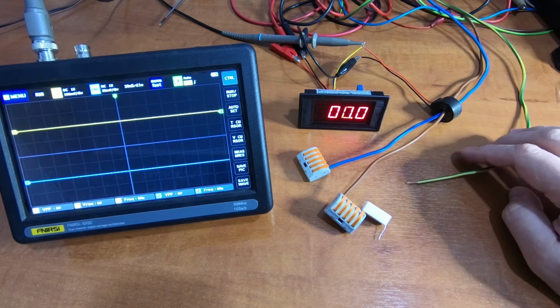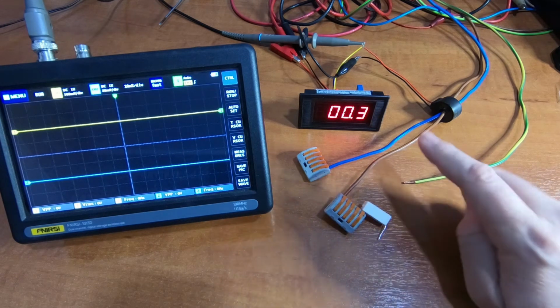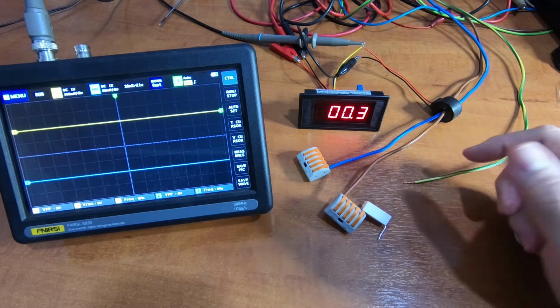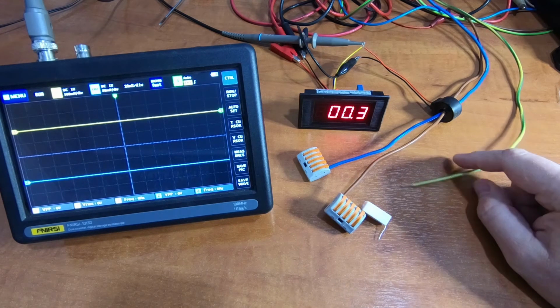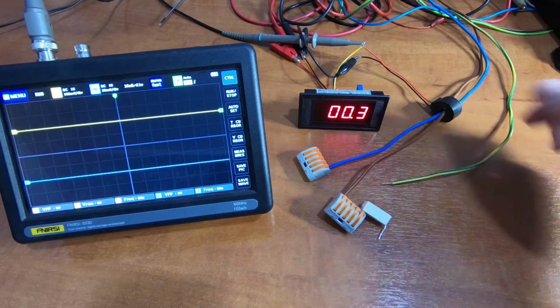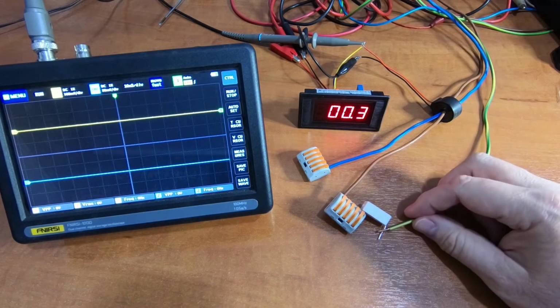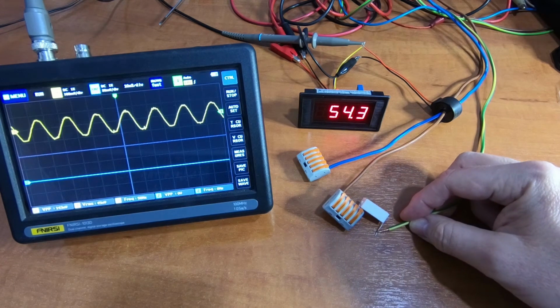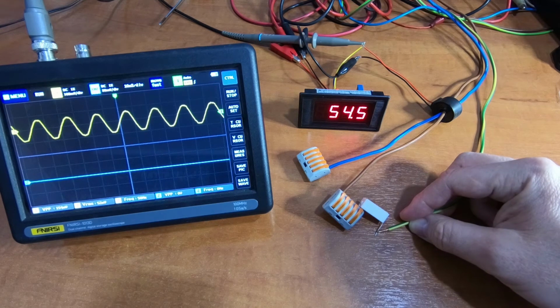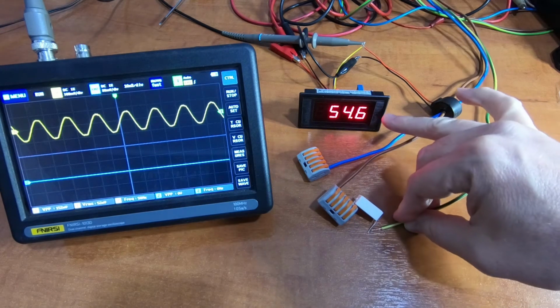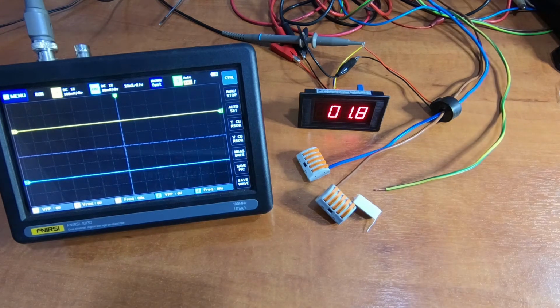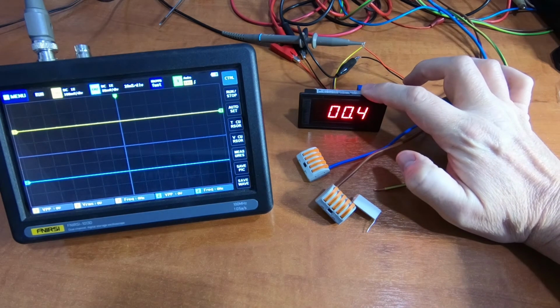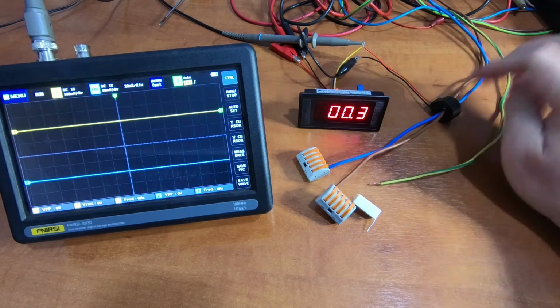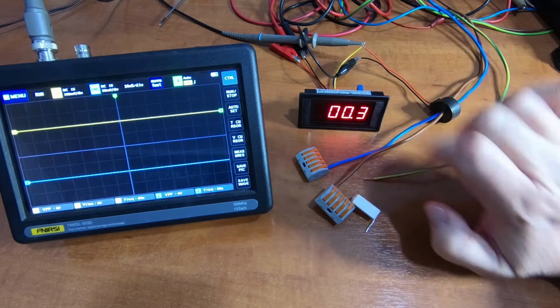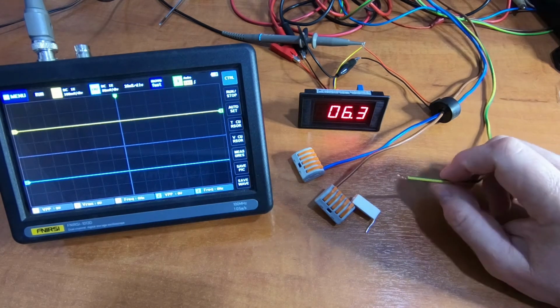So I know from our calculation that 11 milliamps of earth leakage current is flowing through the earth line. What I need to do is calibrate this. I could just say 11 milliamps is 54 on the display, but it'd be nice to dial it in so we get an actual milliamps reading. So I'll experiment with a couple of resistors, maybe a variable resistor, in series or parallel with the current transformer, to adjust the display to match what we know is flowing.